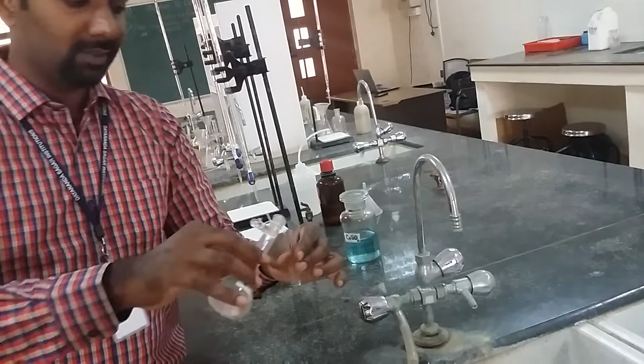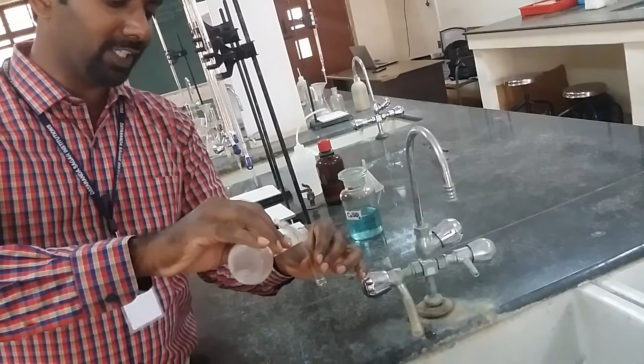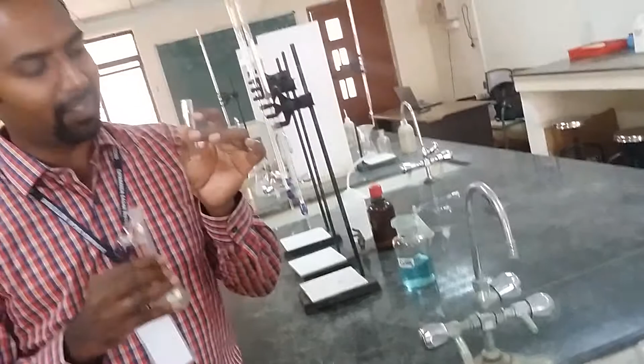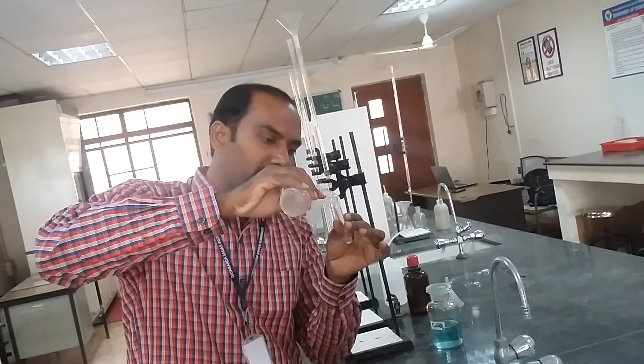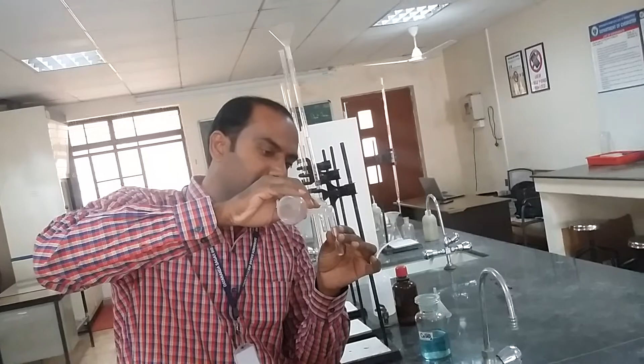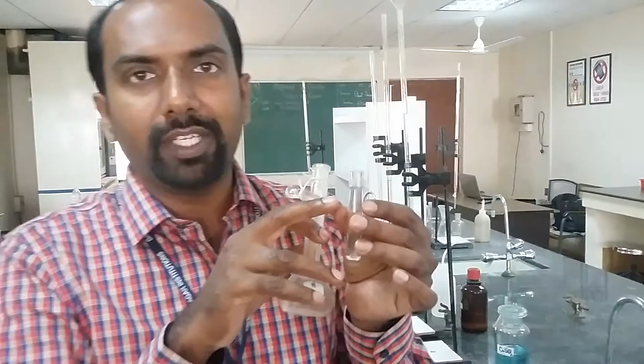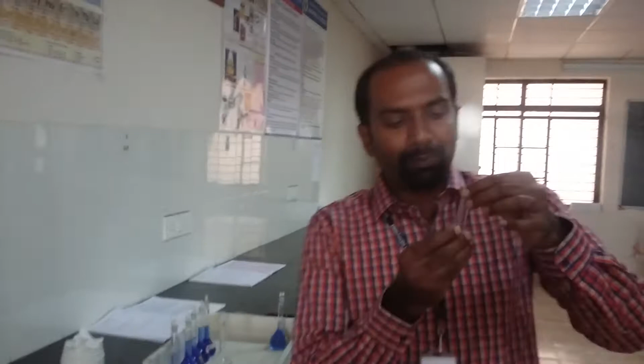Rinse the cuvette two times with the respective solution. After two rinses, we need to take the solution up to 75% of the cuvette. Then we need to wipe this cuvette and clean it. There should not be any fingerprint on this cuvette, and there should not be any dust particle or other impurity on the surface of the cuvette. After wiping and cleaning it, we place the cuvette in the colorimeter.